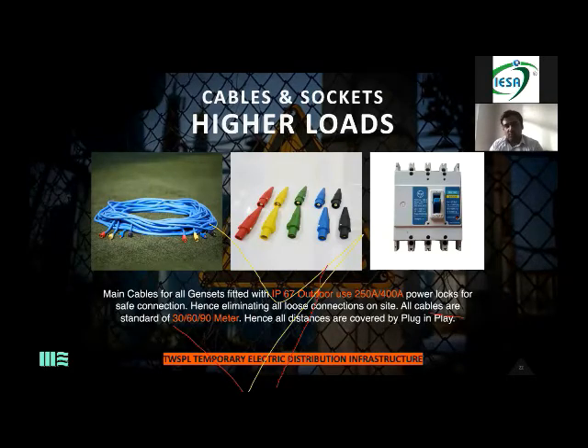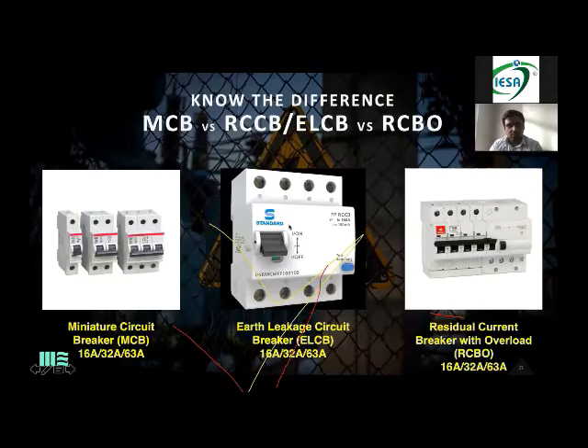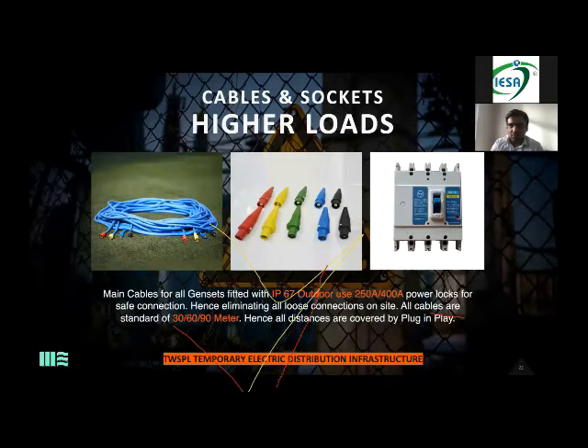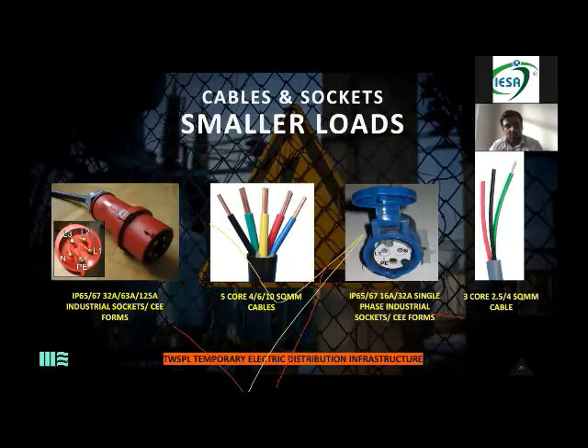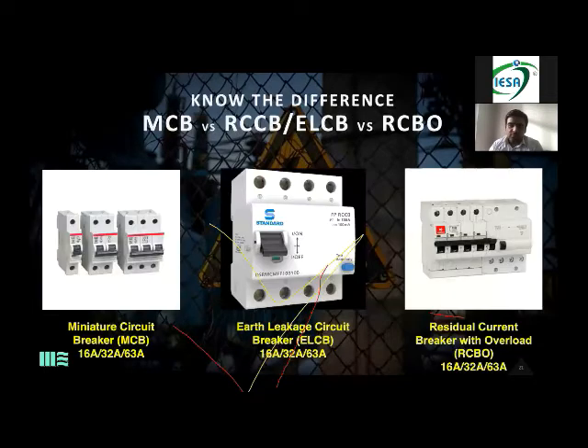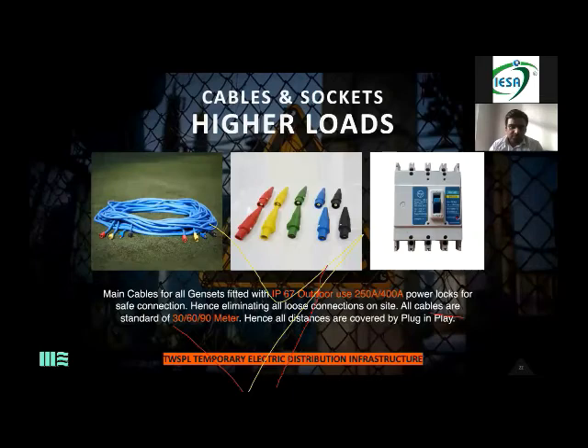Imagine, if you have to connect 4 wires onto this, and you have 1,000 stalls, 1,000 into 4 connections, you're doing 4,000 connections on site. How can it be avoided? If you're using these sockets, it becomes plug and play. You're not doing any connection. First of all, reliability becomes easier because all the homework you've been doing is done in your warehouse. So you don't have to worry about the connection.